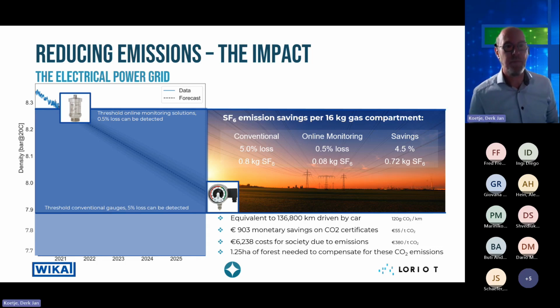What does that mean? If you compare a small compartment of 16 kilograms filled with SF6 gas, you can achieve savings of 4.5%. That means for a 16 kilogram filled compartment, you can save 0.72 kilograms of SF6 gas.